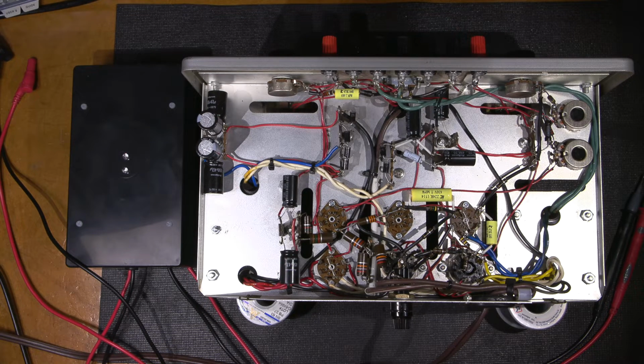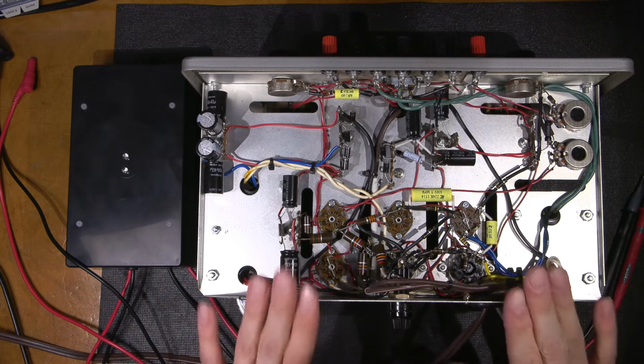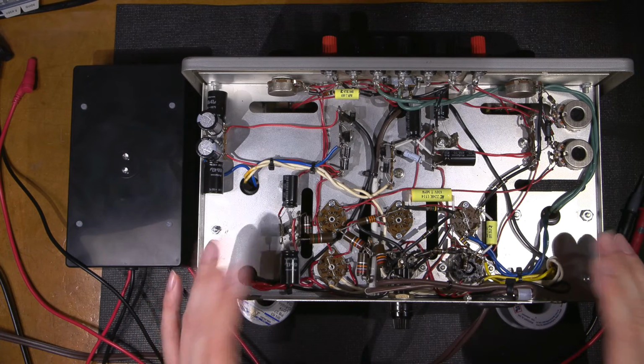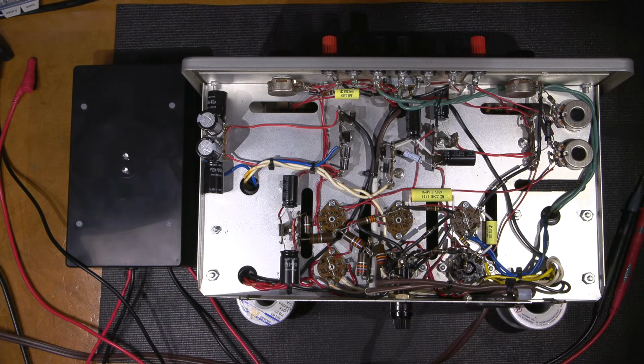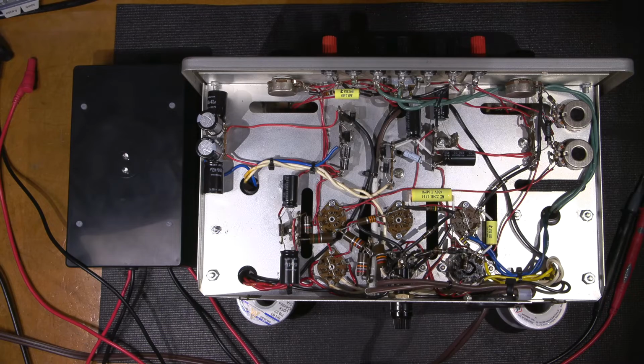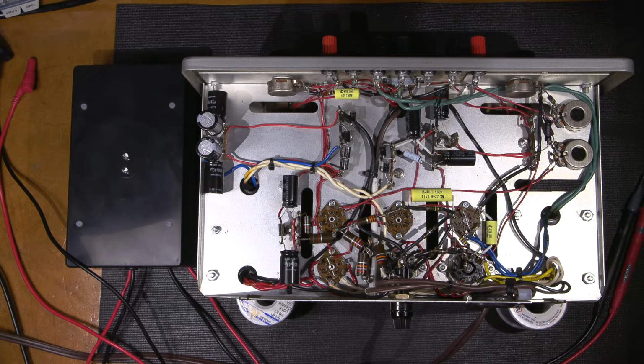Nowadays, that is not up to electrical code at all. Everything has to be isolated, no exposed metal screws or anything like that. So the chassis is hot in those older units, and they need to have an isolation transformer. Now, technically, in a unit like this, the transformers themselves act as isolation from the line, right? Because there's no connection. The chassis in this thing is actually floating. So unless you have that bridge bar on the front, there is no connection to the internal circuitry at all. It really is a floating chassis at that point.